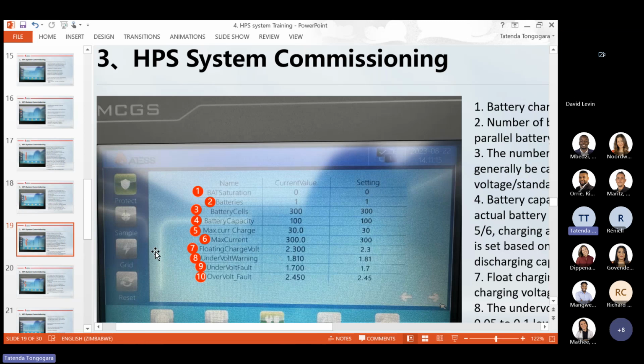And then we have batteries. If you have 5 batteries in parallel that you've connected to your bus bar and then to the HPS, for the number of batteries you write 5. For battery cells, on most batteries the nameplate gives the number of cells in each battery. So you have 5 in parallel and each battery is 160 cells, you just write 160 for one battery. So the inverter will know I have 5 batteries with 160 cells each. For battery capacity, you write the AH value, not the kilowatt hour value. So if you have 5 batteries of 100 AH, you just write 100, the AH value for one battery. I have 5 batteries, it's 100 AH each.